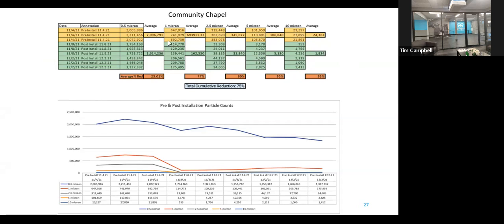Now, one thing I do want to point out, the more particles we have on the larger side, the less reduction we'll see on the smaller side. And that's because those larger particles will actually shadow the smaller particles. That's because of the way a particle counter works, how we actually detect the particles in the air: you have a vacuum that draws the particles in, you measure the particles per cubic meter, and then there's a light that shines to measure the particle size and diameter. So obviously, if there are more larger particles, it's going to hide those smaller particles. So it's just kind of an anomaly in this situation, but nonetheless, as you can see, we still saw massive reductions.